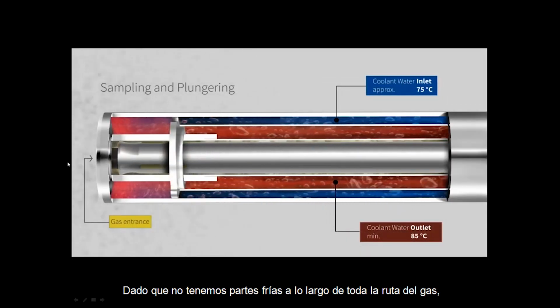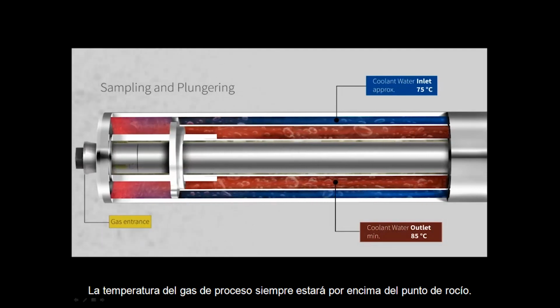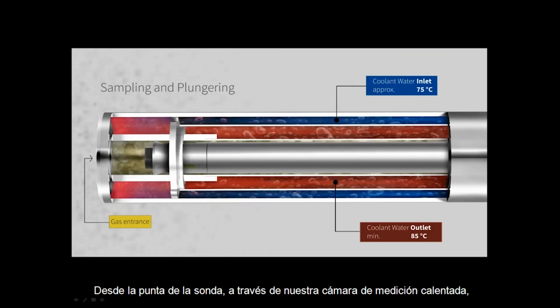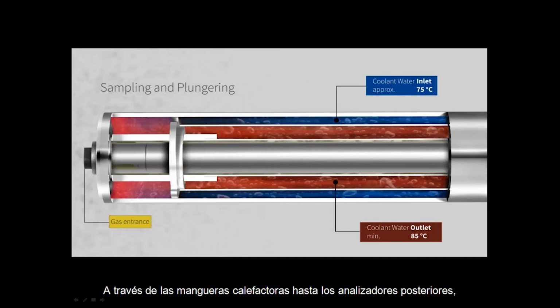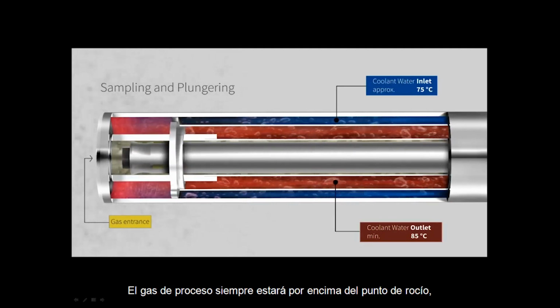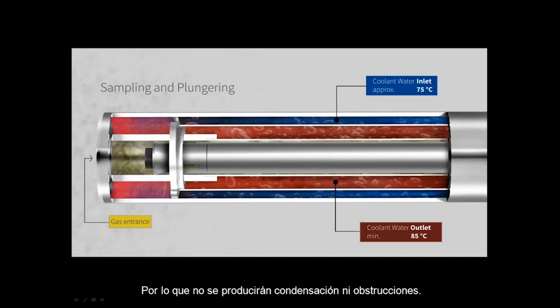Since we have no cold parts along the gas path, the temperature of the process gas will always be above the dew point. From the tip of the probe, through our heated measuring chamber, through the heated extraction lines to the downstream analyzers. The process gas is always above the dew point, so condensation and blockages won't take place.